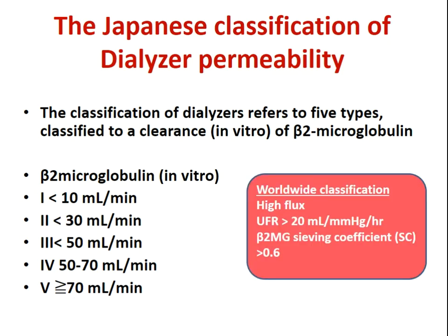The Japanese classification of dialyzer permeability depends not only on small molecule clearance but also on beta-2 microglobulin clearance (middle molecules), classified on a scale from 1 to 5, with 5 having the highest clearance value for beta-2 microglobulin. Another classification of high-flux dialysis depends on an ultrafiltration rate above 20 mL/mmHg/hour and a beta-2 microglobulin sieving coefficient greater than 0.6.